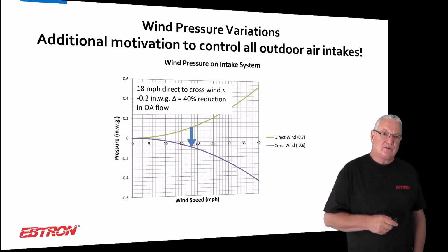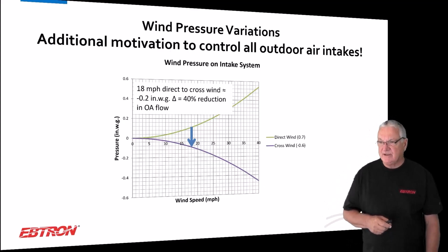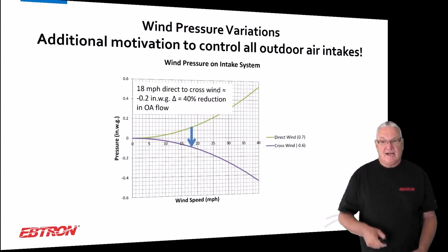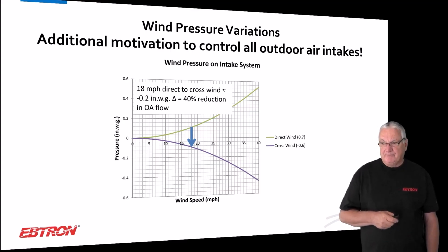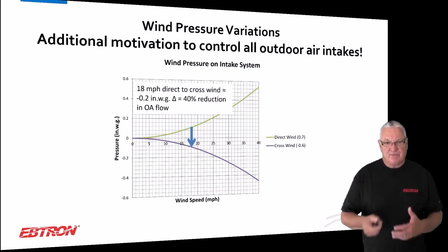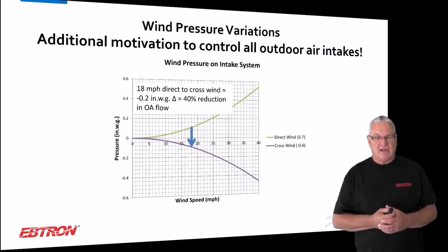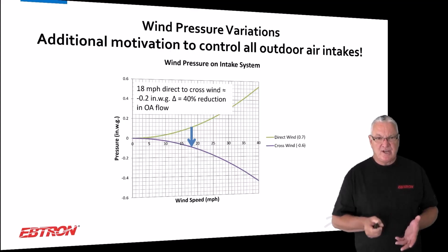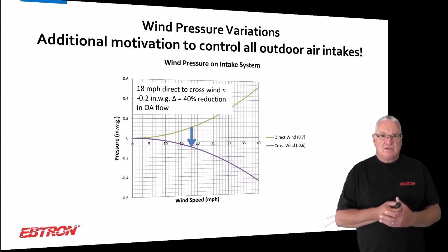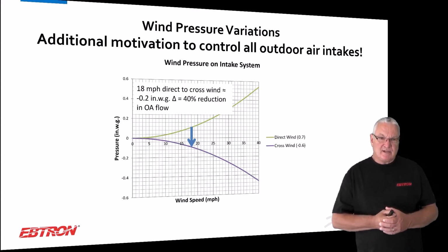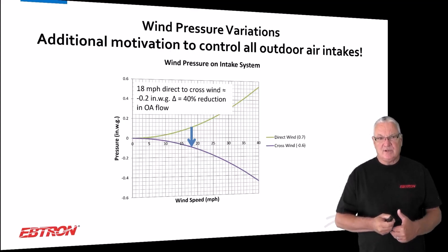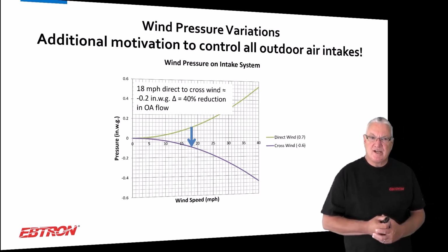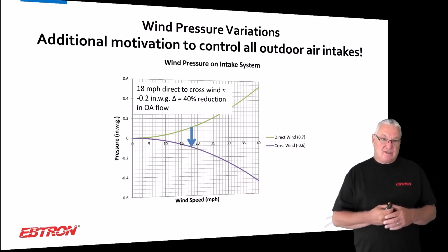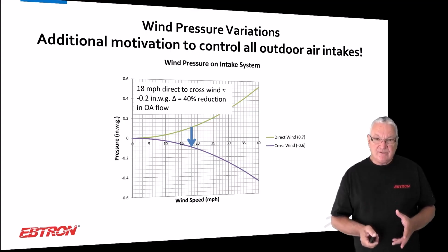And that's why I like to talk to a lot of test and balance people, because it's like, hey, you're going out and you're setting some of these systems up that don't have control or are relying on damper position, and you're having these problems because what you don't realize is that the pressures are changing. So what you set today isn't what's going to happen tomorrow. So here I have an 18 mile an hour direct wind to an 18 mile an hour crosswind is about that same 0.2 of an inch change on that intake system. And so that's a 40% change in the flow.